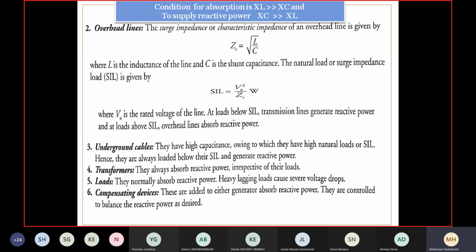That is how the current power electronic technology, FACTS, flexible AC transmission approach, works to modify the reactance of the transmission line itself. We cannot change the transmission line, but we can change its characteristics. The inductiveness can be compensated by adopting alternative capacitive concepts, making it more reactive. The adoption of such mechanisms makes the overhead line intelligent. Whether they are absorbing or delivering is managed by such additional incorporations.